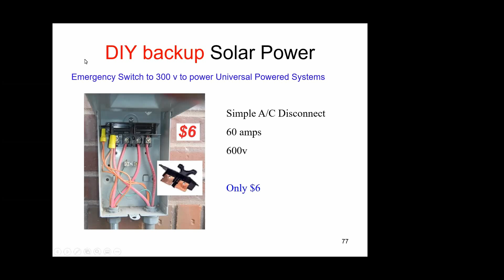High voltage DC is impossible to interrupt because all it will do is form an arc, and the arc will burn until everything around it is burned down, including your house. That's why DC disconnect switches are very expensive — there has to be a quenching system to quench that arc. As I noted, I use the pullout as a method of doing that. Anyway, now you've got 300 volts DC that can power everything modern and universal in your house, except for the stuff you actually need.